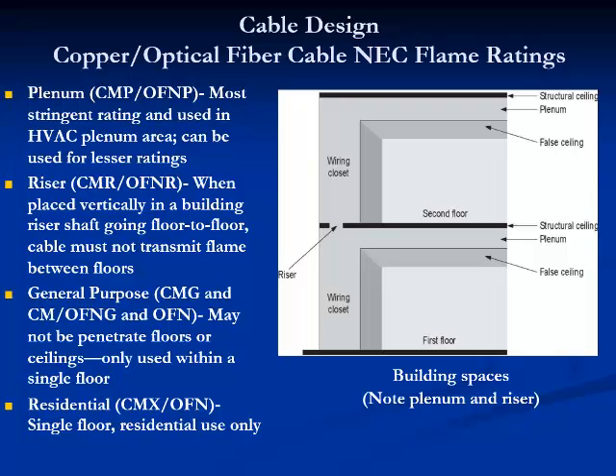Study the area of the building, identify the plenum spaces, then review the fire ratings, which are plenum, CMP for copper, and OFNP for fiber. This is the most stringent rating and is used in HVAC (heating, ventilation, air conditioning) plenum areas, and they can also be used where lesser rating requirements apply.